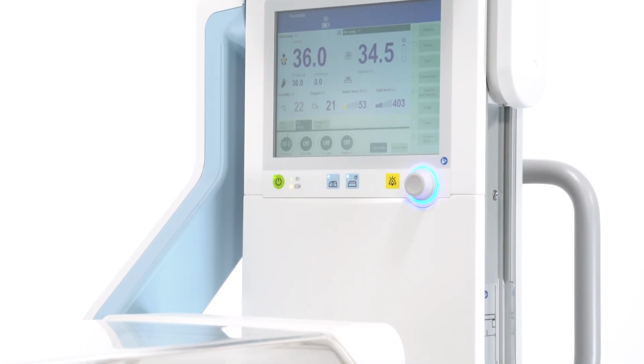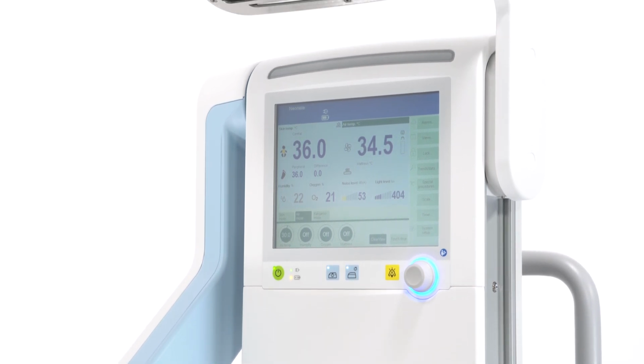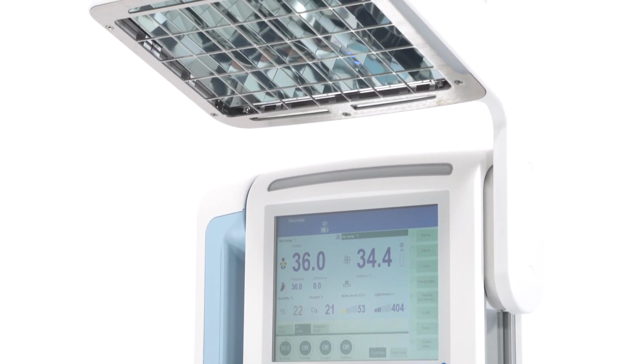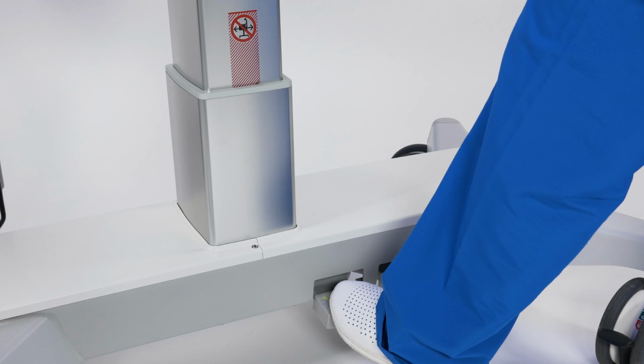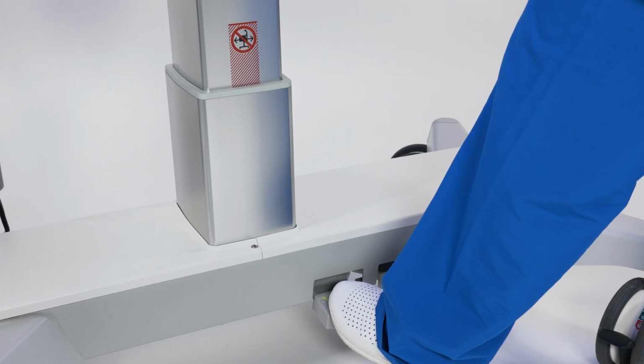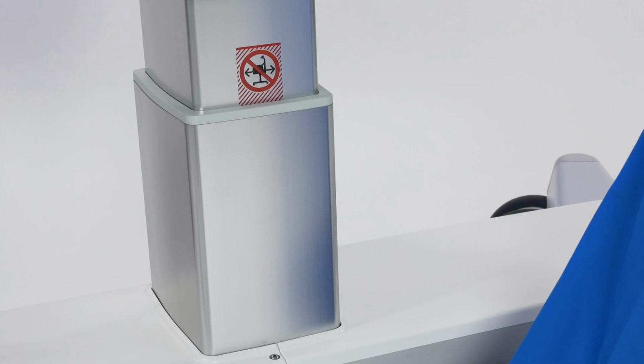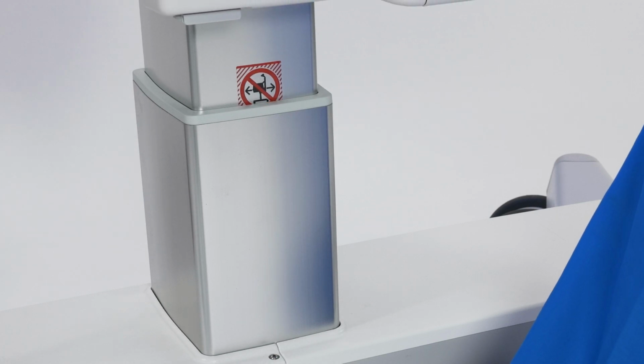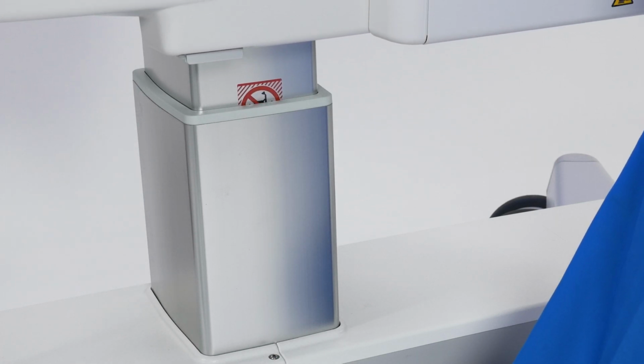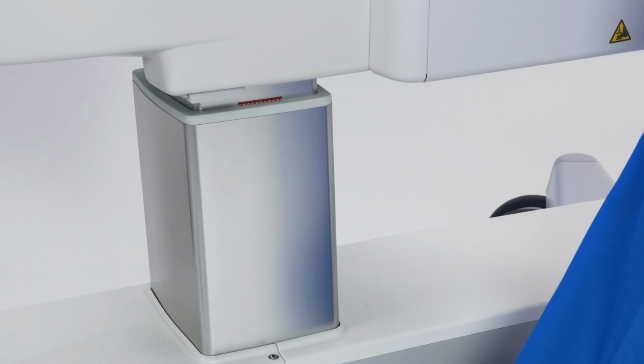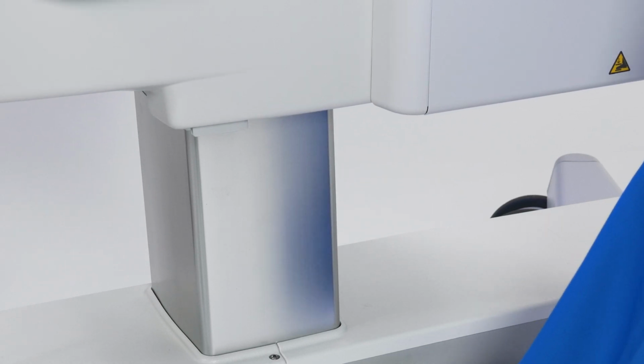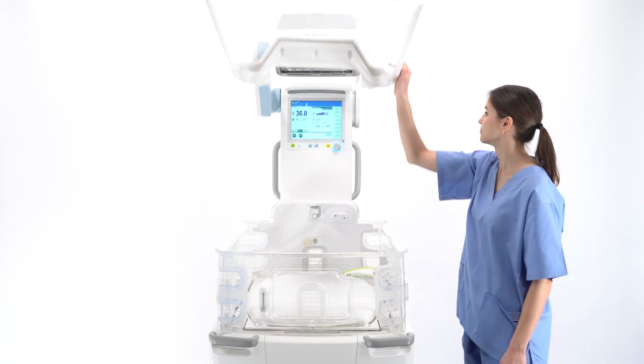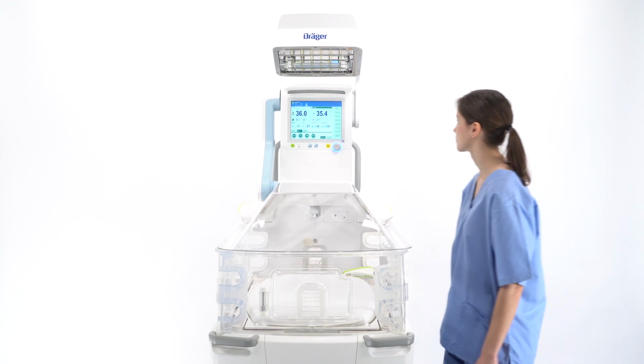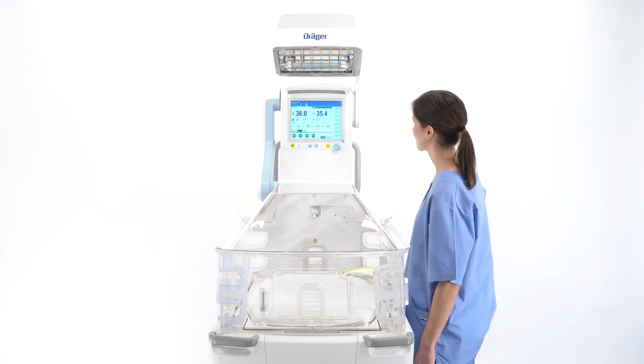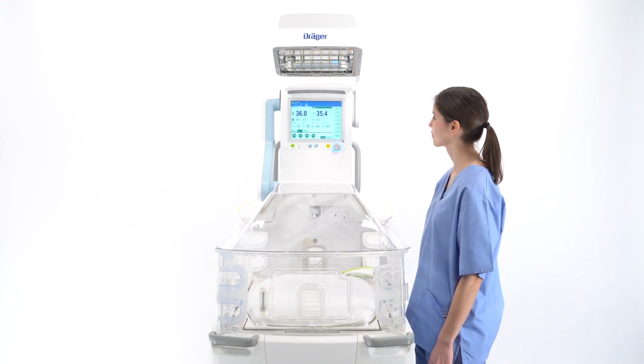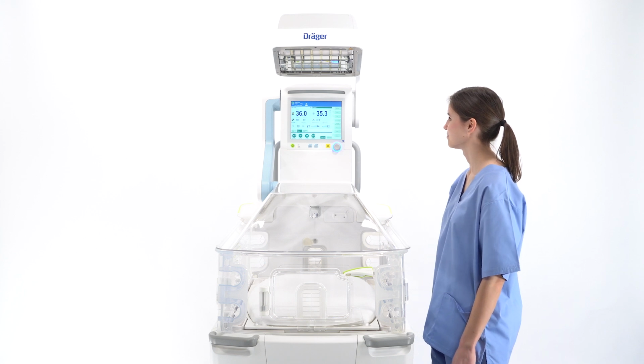Before initiating transport, Babyleo must be prepared in advance. First, make sure the IncuWarmer is set to the correct height for transport. This will prevent it from tipping over. Use the foot pedals to adjust the height until the red hood label is no longer visible on the column. Close the hood and check the settings for temperature and humidity inside the incubator. If necessary, let the incubator warm up until the set air temperature is reached.